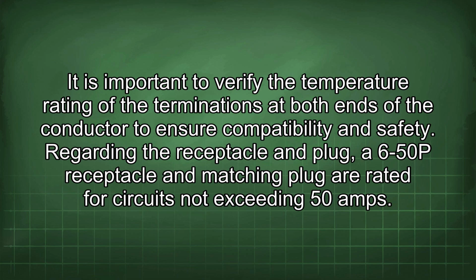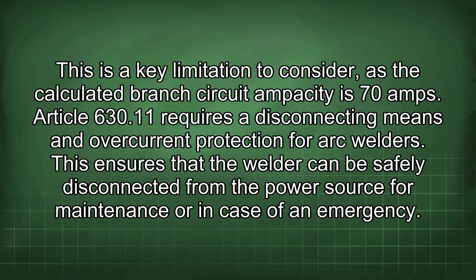compatibility and safety. Regarding the receptacle and plug, a 6-50P receptacle and matching plug are rated for circuits not exceeding 50 amps. This is a key limitation to consider, as the calculated branch circuit ampacity is 70 amps.